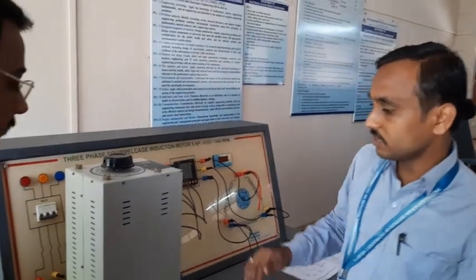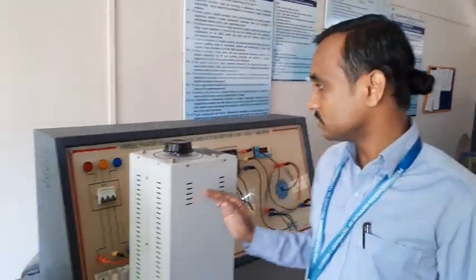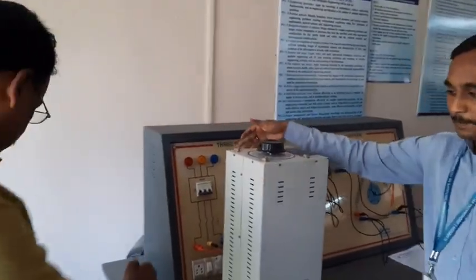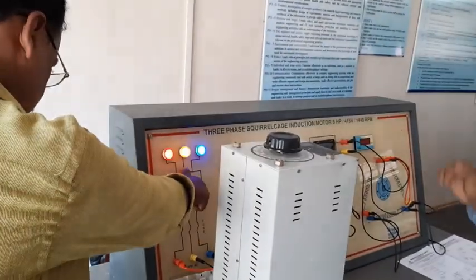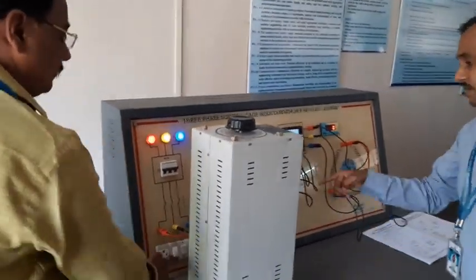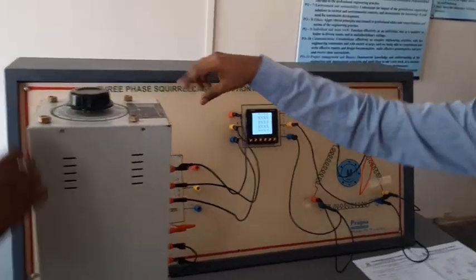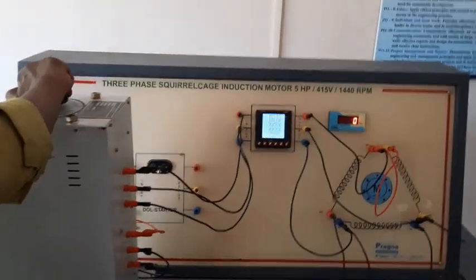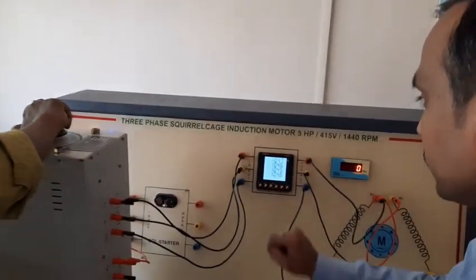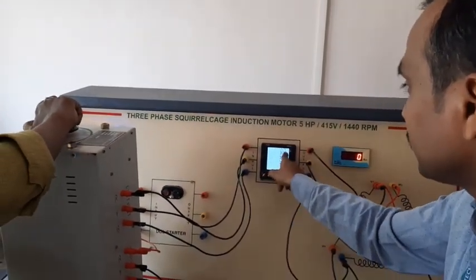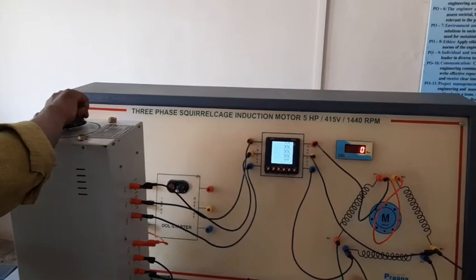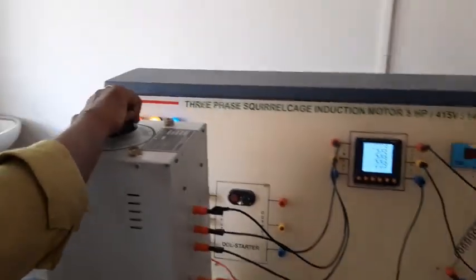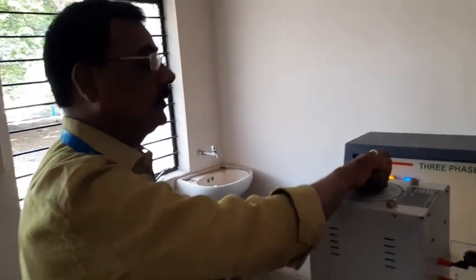First, initially you start with the no load. So switch on the supply. Okay, meters on. Slowly apply the rated voltage of 415 volt. Press the voltage button. That is the voltage in between R to Y phase, and that should be 415 volt.